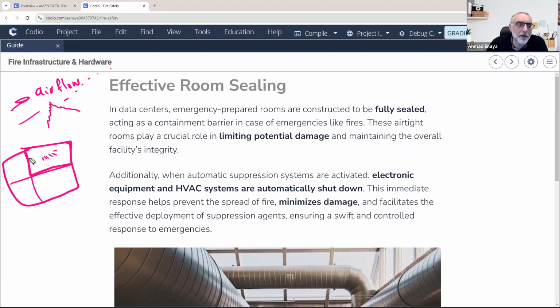But on the other side, we have ventilation, we have a plenum, we have a lot of open spaces between these rooms. So if you want to be able to control fire faster and to limit the spread of fire, we need to have some sort of sealing between rooms, and mainly in the important rooms. If we have several rooms that we want to be safe in case of fire in other places, we want to have these rooms fully sealed, so in case of fire in other rooms, the fire doesn't extend to these rooms.